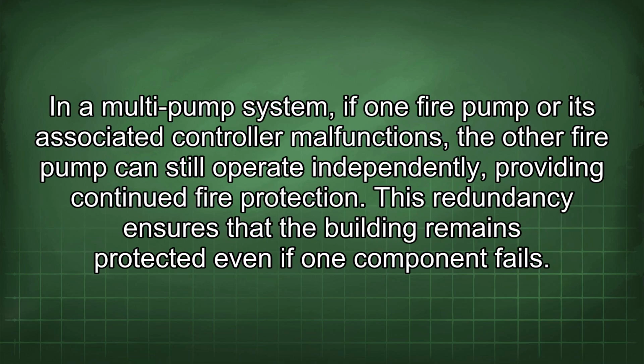The redundancy and reliability offered by having an individual ATS and fire controller for each fire pump are paramount. In a multi-pump system, if one fire pump or its associated controller malfunctions, the other fire pump can still operate independently, providing continued fire protection. This redundancy ensures that the building remains protected even if one component fails.